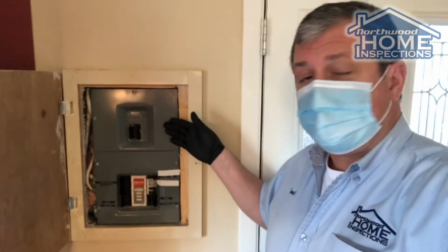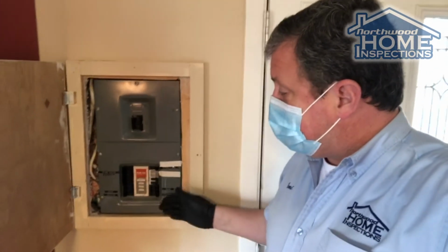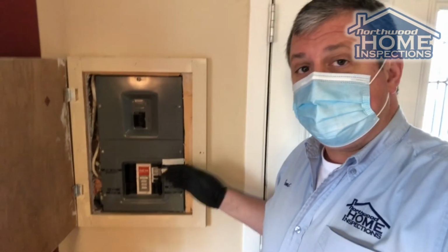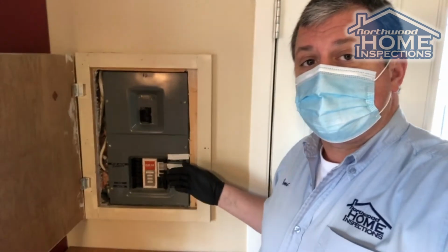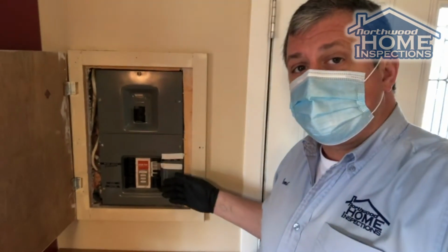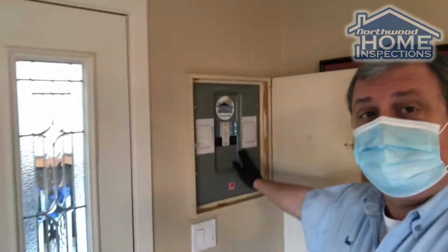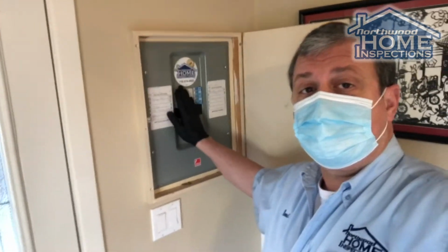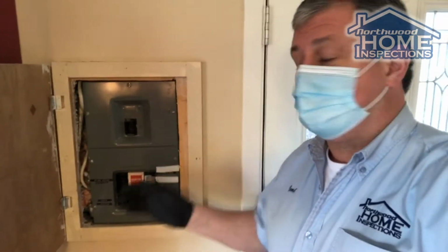Now in this case, about 20 years ago, these homeowners actually did a kitchen renovation. So they have no breaker space for additional circuits for a modern kitchen. In 1968, they typically were not installing all of those dedicated circuits for things like fridges and dishwashers and dedicated counter plugs. Now, the way that they did that renovation is they actually added this sub panel. That was enough for the sake of those extra circuits for that renovation. And now, of course, all of this is full.